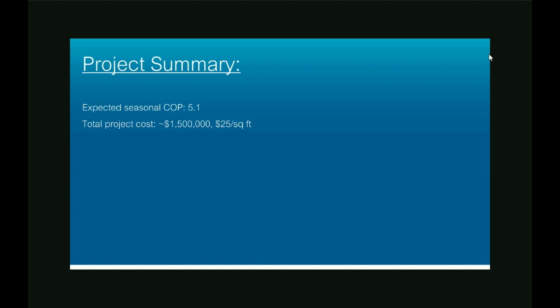Here's my favorite slide, and it is basically my last slide here. The overall expected efficiency is a 5.1. 5.1 for a building with existing hot water. That's unheard of. That's exceptionally high. And at a project cost of $25 per square foot, which is also very, very cost competitive. That number, by the way, is before the 40% rebate, before any NYSERDA incentives, before any of the utility rebates. This is a very, very good one. If they had just gone and replaced their boilers instead, it almost would have been the same cost.